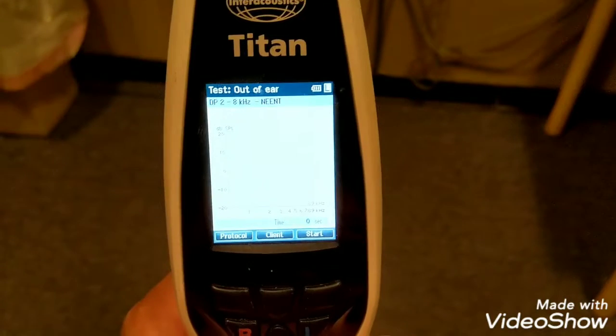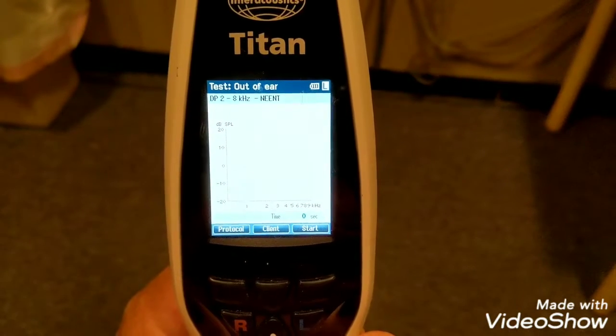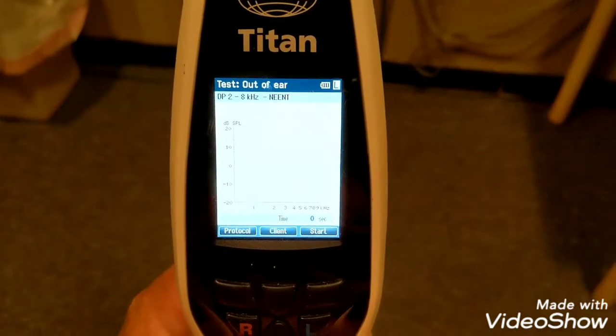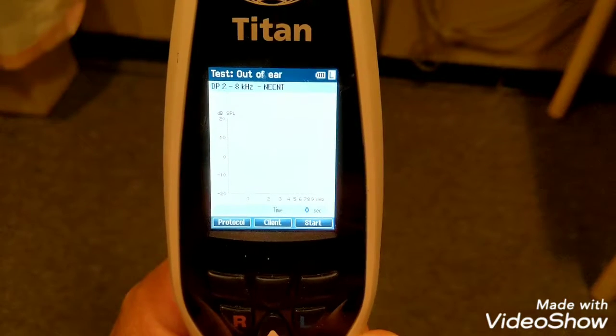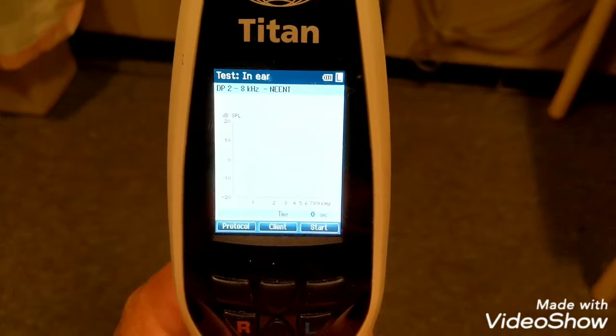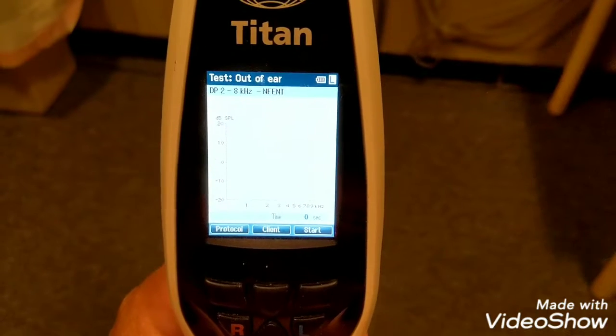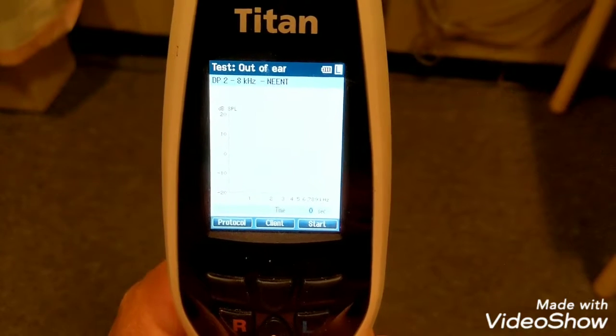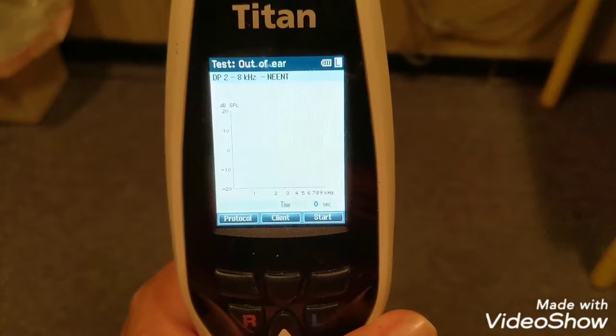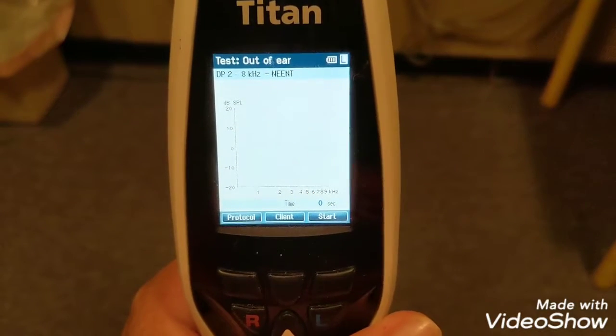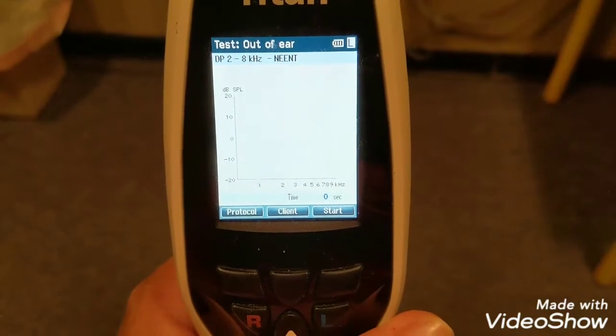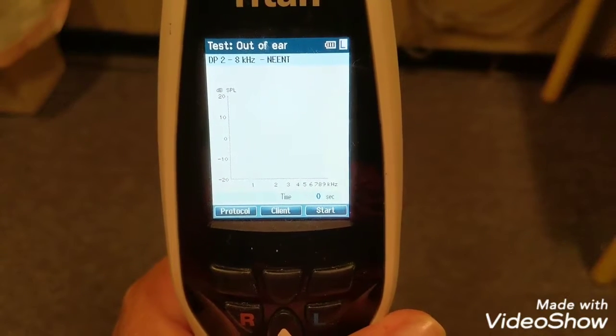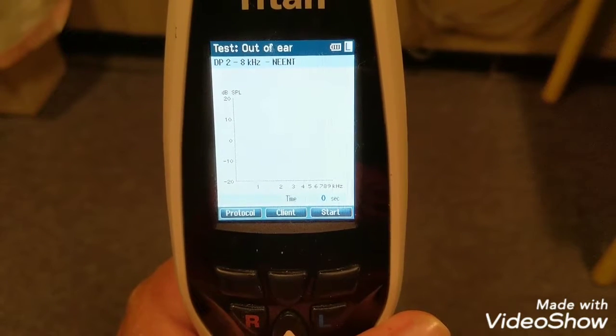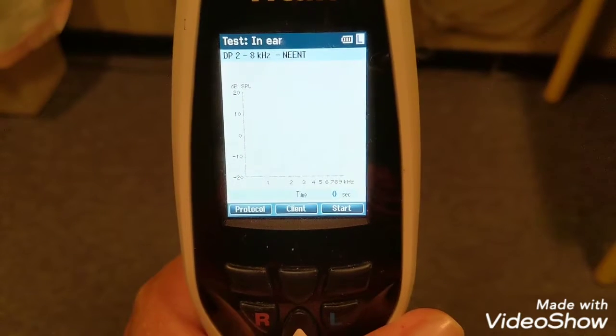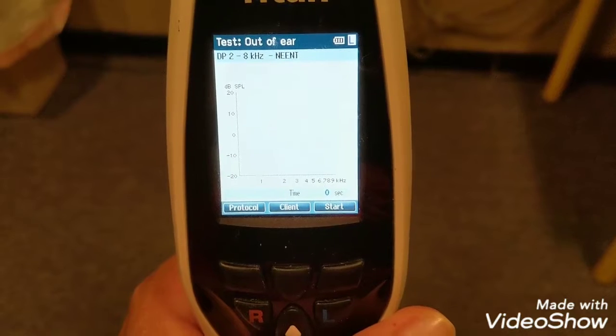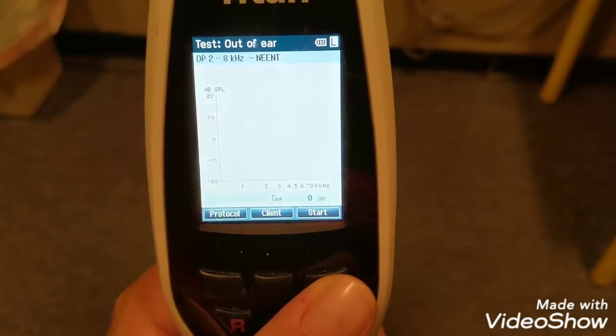The final test I'd like to show you today is actually distortion product otoacoustic emissions, or DPOAEs. DPOAEs are frequency specific, which means I'm testing a very specific range within the ear, and they measure the response of the outer hair cells within the ear to the sound that is presented by the machine. So I'm going to be measuring my own ear again, and I'm measuring 2,000 to 8,000 hertz, so relatively high frequency. And I'll need to sit very quietly as the sounds are presented to my ear and measured from my ear. There's a noise floor that you can see along the bottom that's a dark gray color, and the noise floor goes up if I'm noisy. So I'll be very quiet initially, and then I'll make some loud sounds, and you can see the response change to the test.